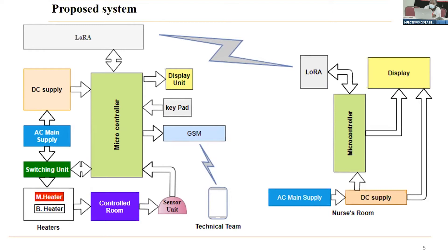The heaters are connected in two pairs — one currently serving the room and the other as a backup. If one fails, the microcontroller automatically switches on the backup heater to continue serving the room, while simultaneously sending a short message via GSM network to inform the technical team about the fault. This room information is also shared in real time to the nurse room using LoRa technology.